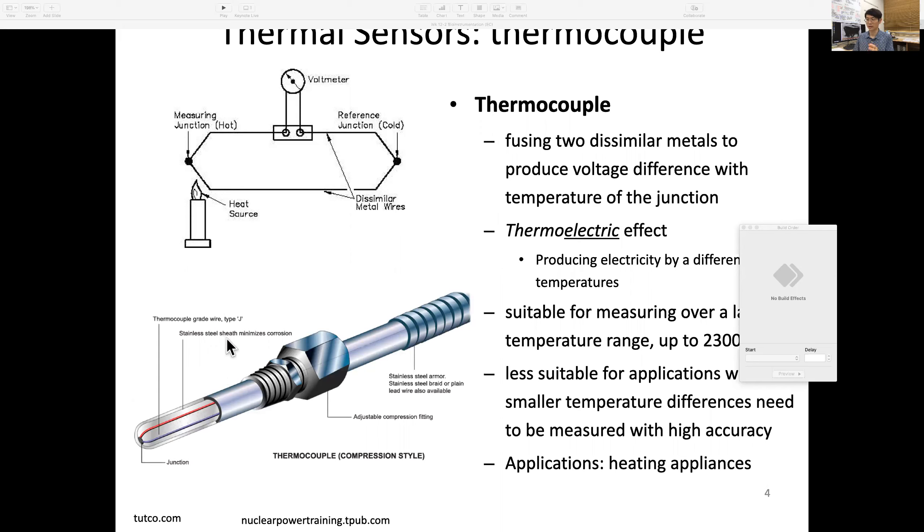This is shielding with stainless steel. You can see the red and blue metal wires with a junction—that's the sensing point. This one is suitable for measuring over large temperature differences, such as up to several thousand degrees.